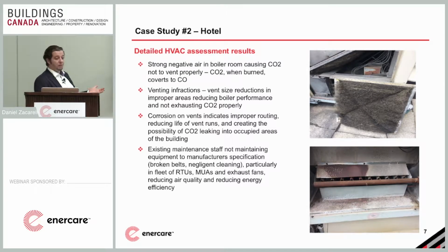If a room is filled with carbon monoxide, you have matters of seconds to get out of there before you lose consciousness and you can lose your life. So with this issue, it's partially in regards to not proper ventilation in the room, not proper combustion air in the room, sized by your boilers and the HVAC equipment that you have in that room. There has to be, by code, a specific amount of combustion air coming into that room, ducted to a specific area within 18 inches of the floor, for example, within that room, and we saw that these issues weren't there.